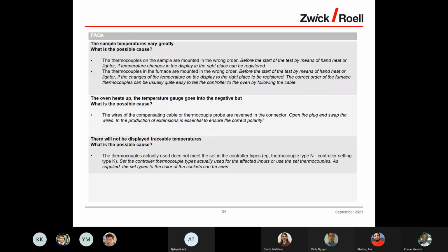The sample temperatures vary greatly. What is the possible cause? The thermocouples on the sample are mounted in the wrong order. Before the start of the test, by means of hand heat or lighter, I prefer the lighter, check if temperature changes in the display can be registered in the right place.